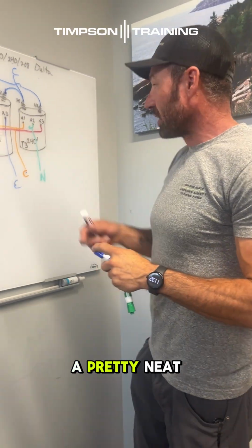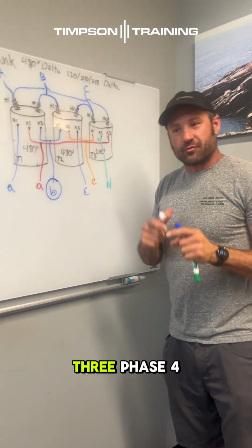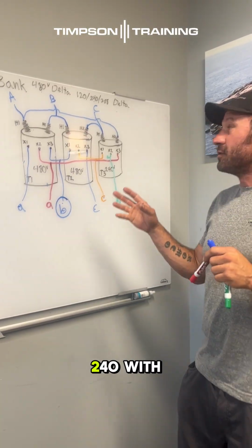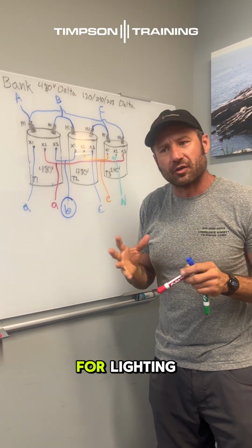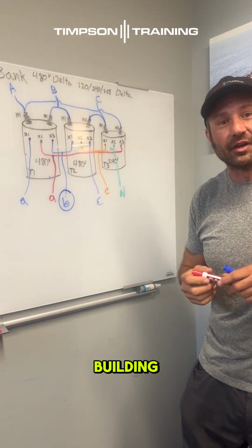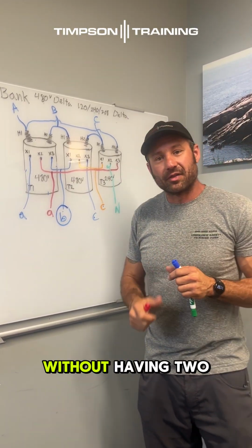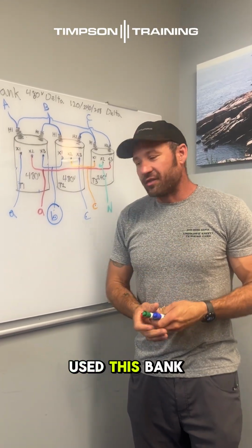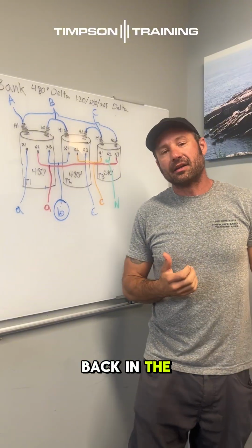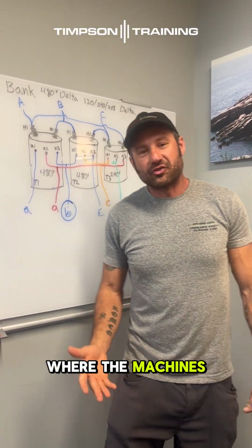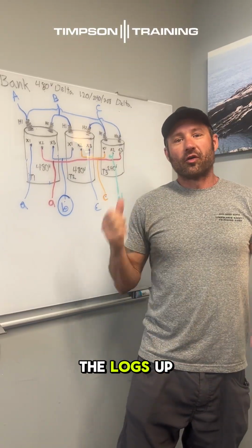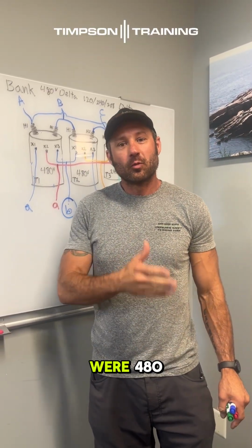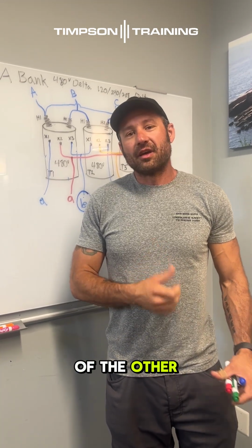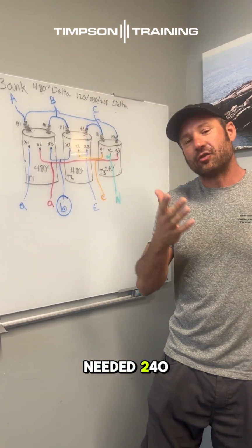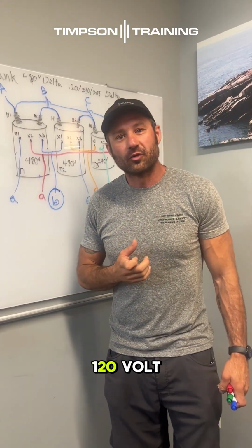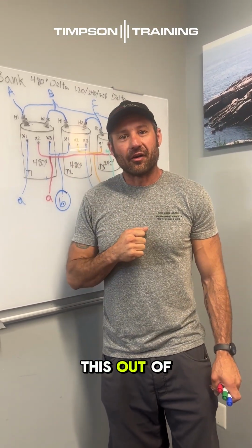So this is a pretty neat way to get three-phase 480 and three-phase 240 with a neutral, so you can have 120 for lighting and regular things inside of a building, all out of the same transformer bank without having two banks. That's why they used this bank primarily back in the day in the timber falling industry, where the machines, the heavy equipment that would pull the logs up the hill so they could load it onto trucks, were 480 volt. And then some of the other smaller machines and the offices needed 240 volt and also needed the neutral for 120 volt. So they would do all of this out of one bank.